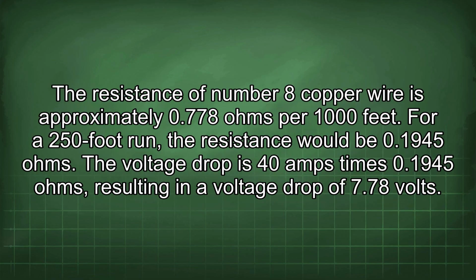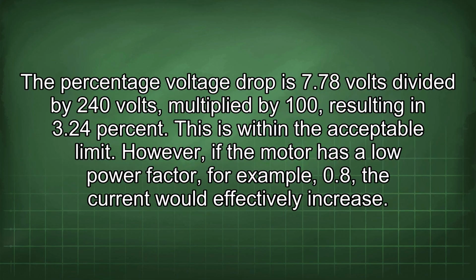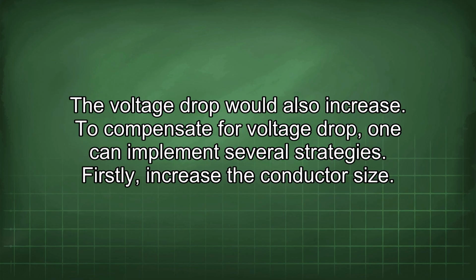The resistance of number 8 copper wire is approximately 0.778 ohms per 1000 feet. For a 250-foot run, the resistance would be 0.1945 ohms. The voltage drop is 40 amps times 0.1945 ohms, resulting in a voltage drop of 7.78 volts. The percentage voltage drop is 7.78 volts divided by 240 volts, multiplied by 100, resulting in 3.24%. This is within the acceptable limit. However, if the motor has a low power factor, for example 0.8, the current would effectively increase. The voltage drop would also increase.